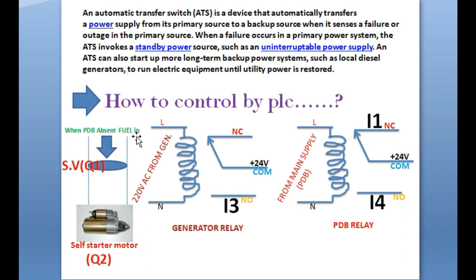This is the main PDB input for the start of the generator. When PDB, that means electricity, is absent, at that time the solenoid valve is on, that means Q1 is on after 5 seconds, 0.2 seconds, or 3 seconds, depending on your programming. The self-starter motor is Q2, that is on, and that means your generator will be started. And then the generator relay: this is a 220 supply from your generator, AC line and neutral from your generator source. When the generator is on, this relay will be on.